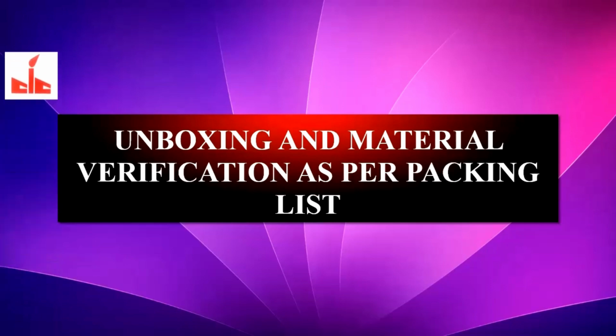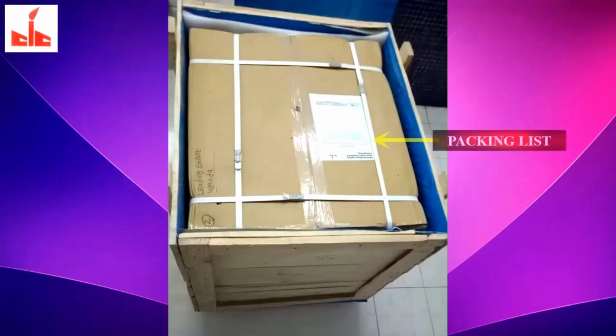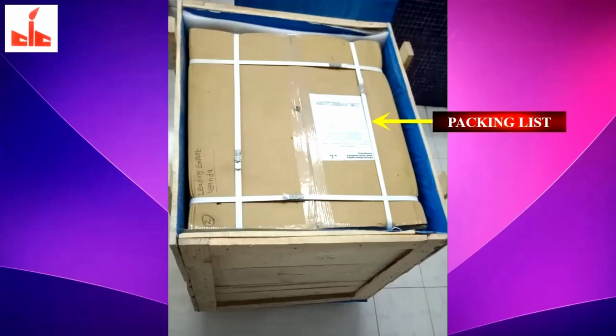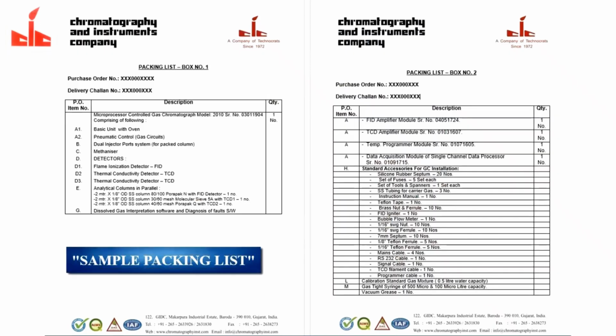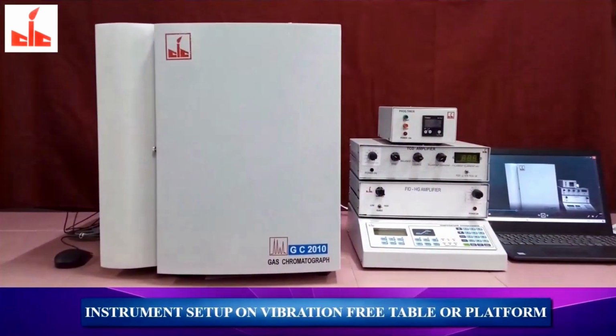Unboxing and material verification as per packing list. Once all the installation availabilities are confirmed, then go for unboxing and material verification as per packing list. The boxes are already received in well-packed condition, as per picture. After unboxing the system, you must check all the material as per packing list. In case of any shortage or discrepancy, immediately contact the organization by audio or video call. Set up the instrument on a vibration-free table or platform for sturdy operation of the instrument.